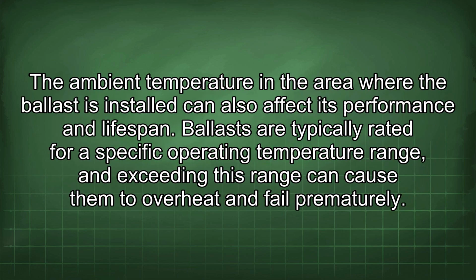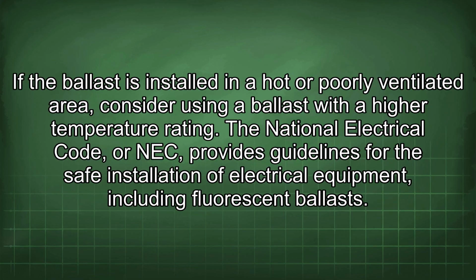The ambient temperature in the area where the ballast is installed can also affect its performance and lifespan. Ballasts are typically rated for a specific operating temperature range, and exceeding this range can cause them to overheat and fail prematurely. If the ballast is installed in a hot or poorly ventilated area, consider using a ballast with a high temperature rating.